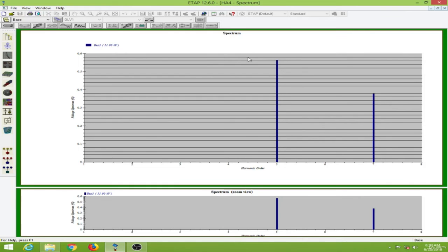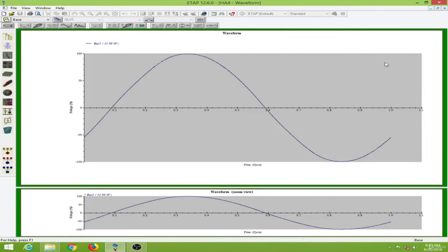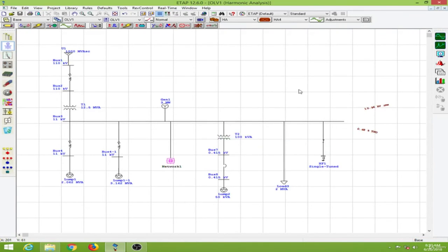Now as you can see, the fifth order harmonic has been reduced significantly. This value is about 0.56, so it has reduced from 0.64 to 0.56. That's the improvement in the waveform.